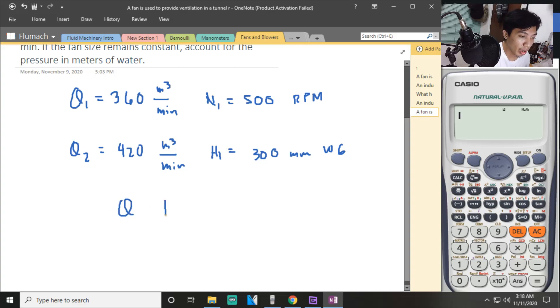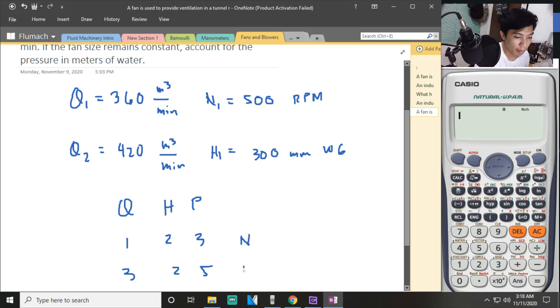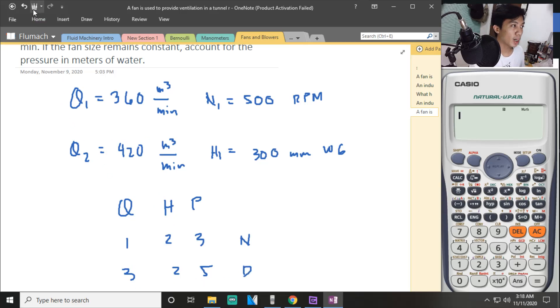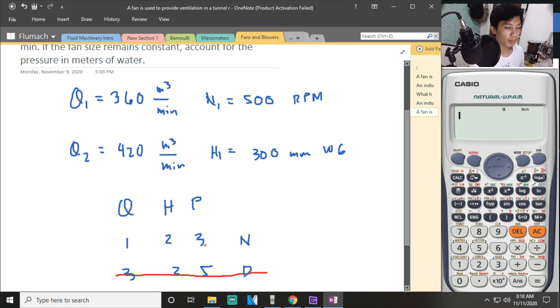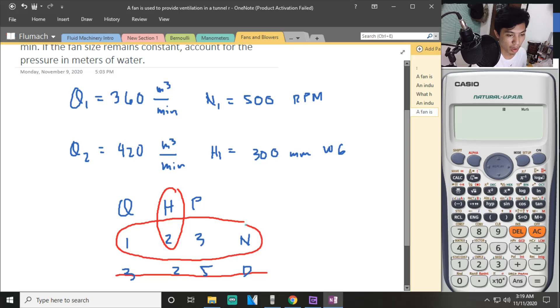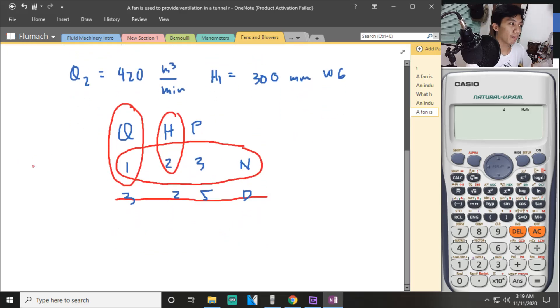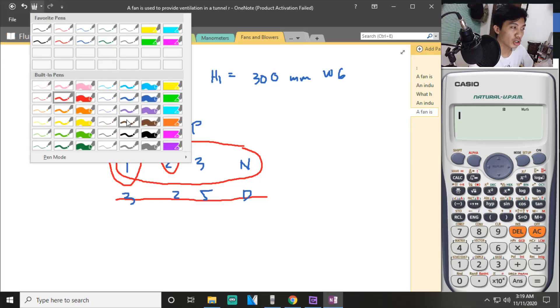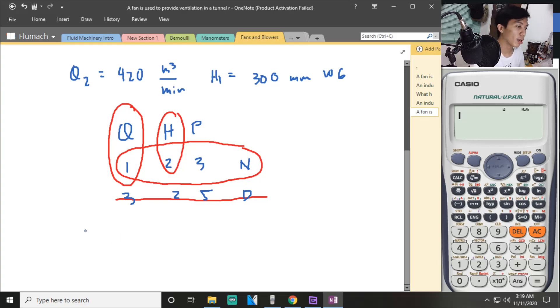So let us list down what we need to find. No temperature was given, so we can use the Q, H, and P affinity law relations. Since we have the same fan size, we can cross out that term. The quantity we want to find is the head H2, but the problem is we don't have N2 — we have two Q values, so we start from there to find the missing N.